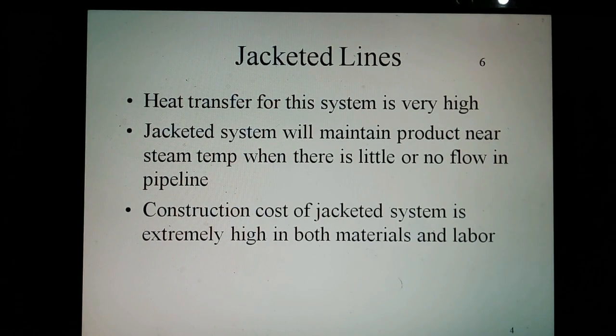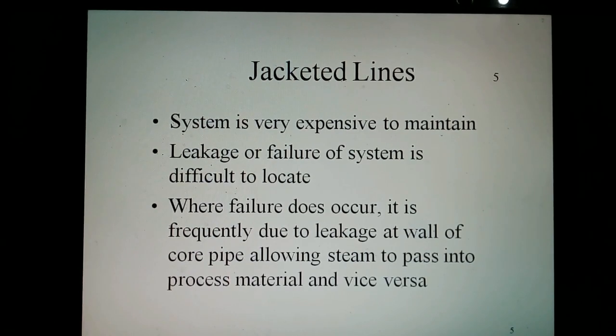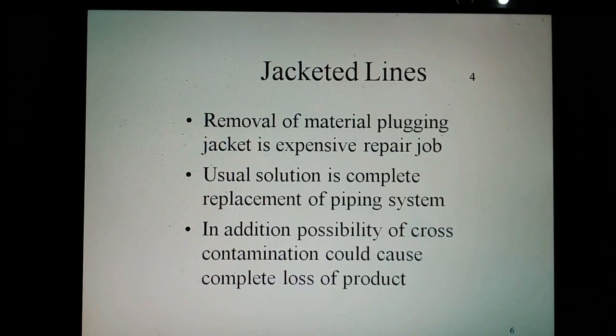On the negative side, the construction cost of a jacketed system is extremely high in both materials and labor. The system is very expensive to maintain. Leakage within the system is difficult to locate. Where failure does occur, it is frequently due to leakage at the wall of the core pipe, allowing steam to pass into the process material and vice versa. The removal of materials from the jacket is an expensive repair job, and the usual solution is a complete replacement of the piping system.